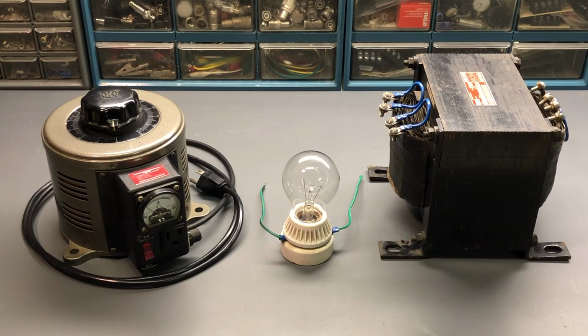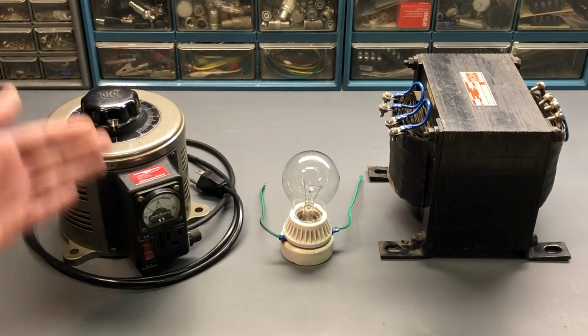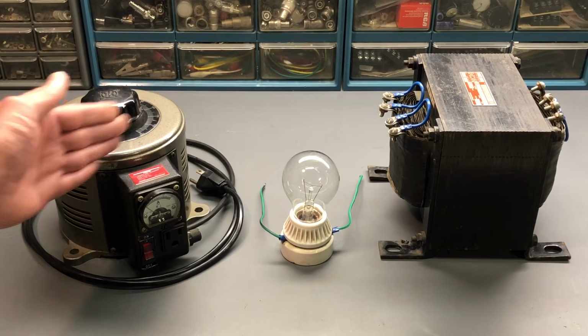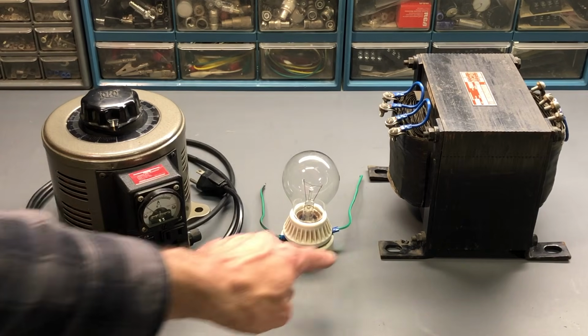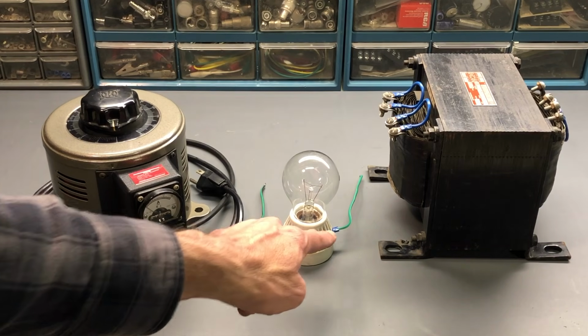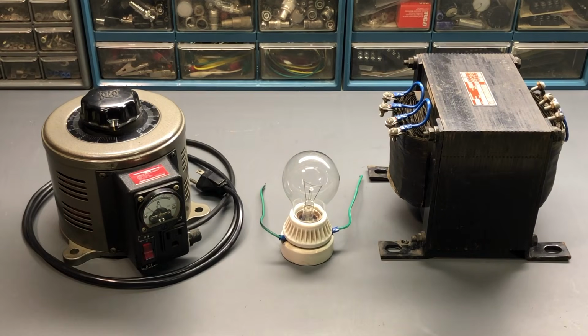That also allows you to use this arrangement on testing modern pieces of equipment where you want electrical isolation, you want to set the line voltage precisely, but you don't need the current limiting. So again, a switch that jumps across the bulb is a very good idea. And again, I'll show my setup that I have, and I do have a toggle switch that is across the bulb that allows you to select the current limiting or not.